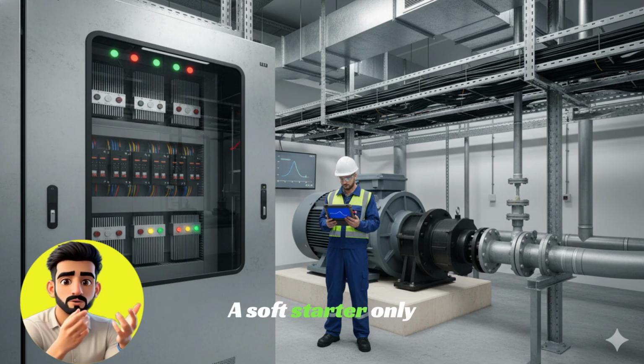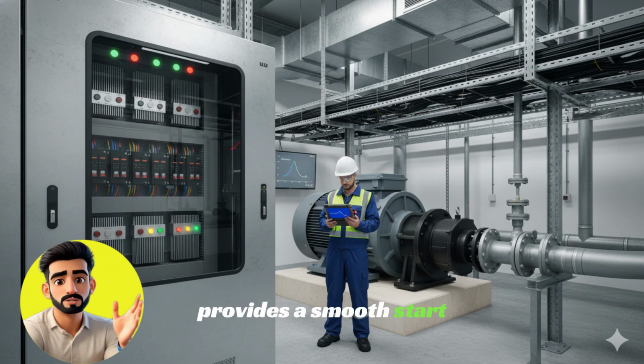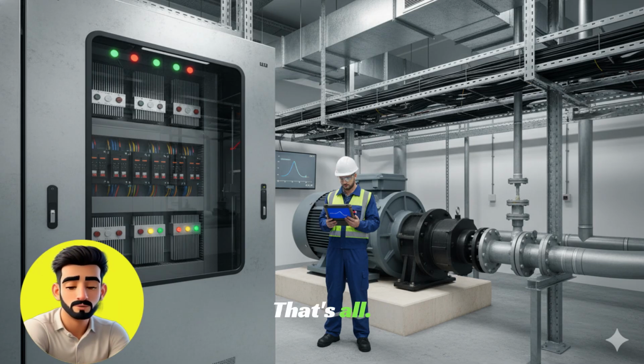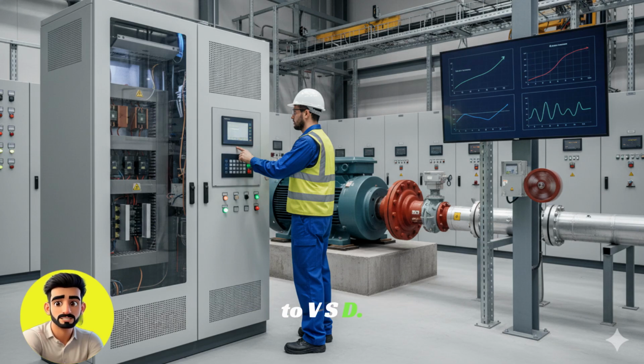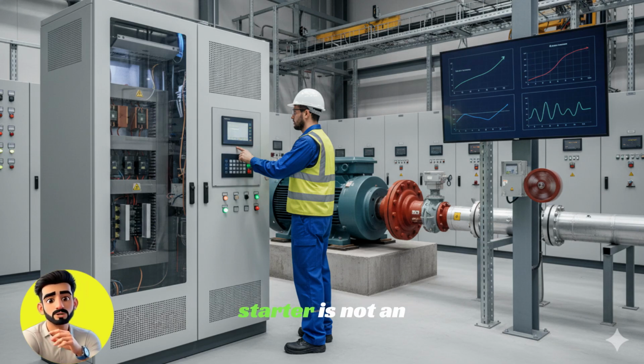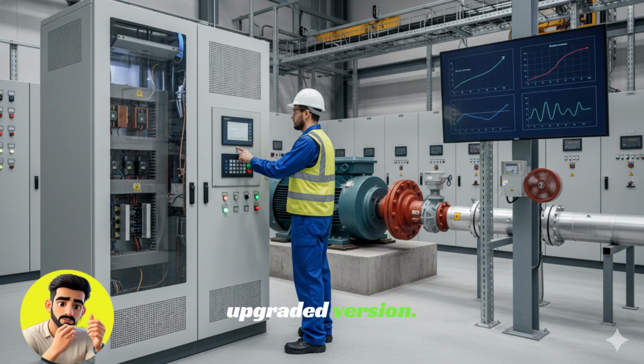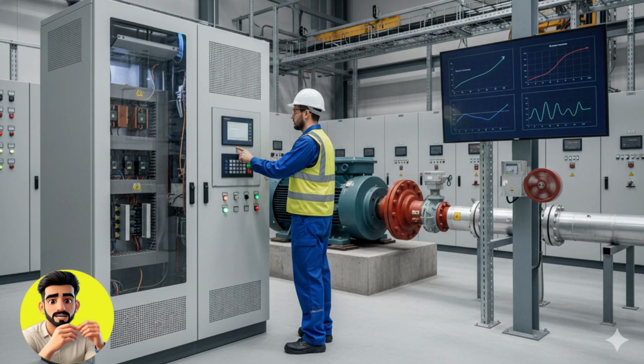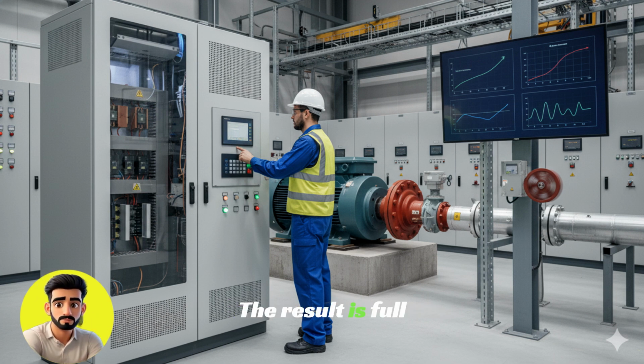A soft starter only provides a smooth start and smooth stop. That's all. Now let's move on to VSD. VSD is not an upgraded version of a soft starter. It is a completely different philosophy. When you use VSD, you control the frequency. Frequency control means speed control, and speed control means torque control. The result is full control over the motor's behavior.